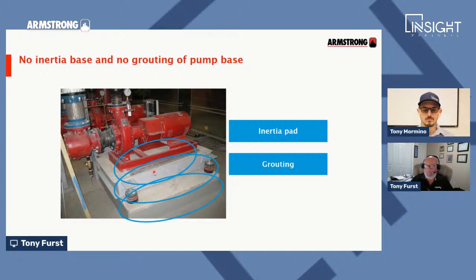The other problem is when you have inertia bases, which are in seismic zones and other places with vibration sensitivity, inertia bases take a lot to get set up correctly and get the springs adjusted properly so the inertia base isn't actually resting on the concrete floor. I don't know how many times over the years I've walked into mechanical rooms where owners are complaining their pumps are noisy, they can hear the pumps on the floor below or out in the hallway. You go in and the inertia base is resting on the housekeeping pad because somebody didn't set the spring isolators up correctly. If you go to vertical inline pumps, you'll eliminate all of that issue.